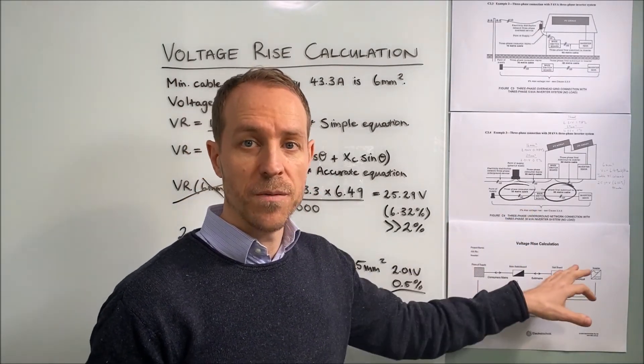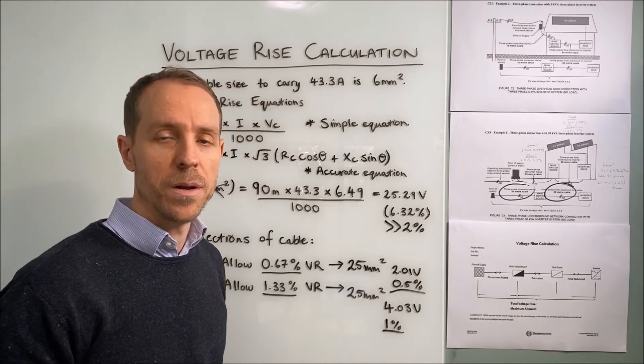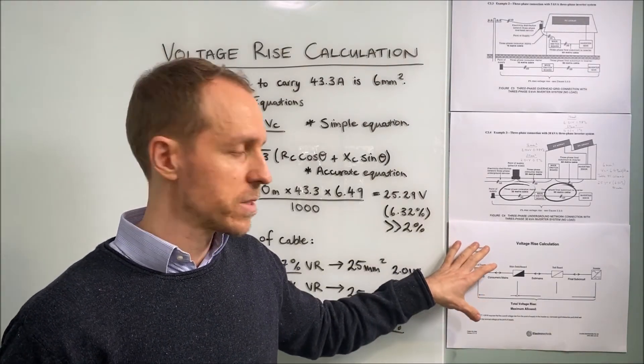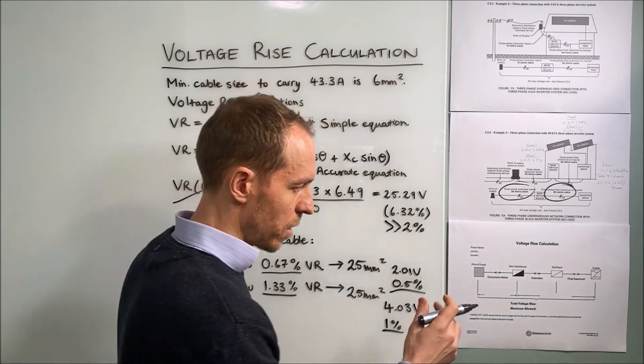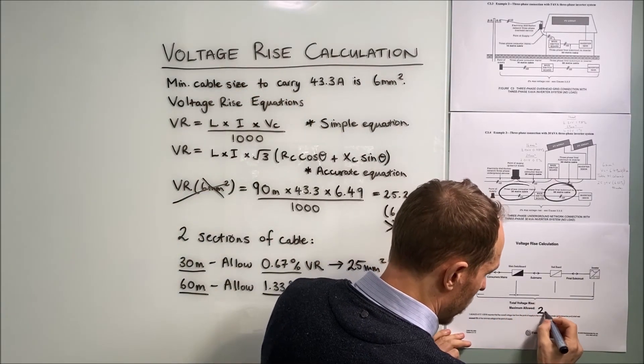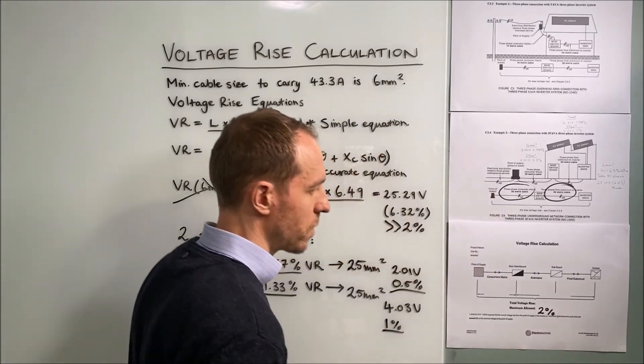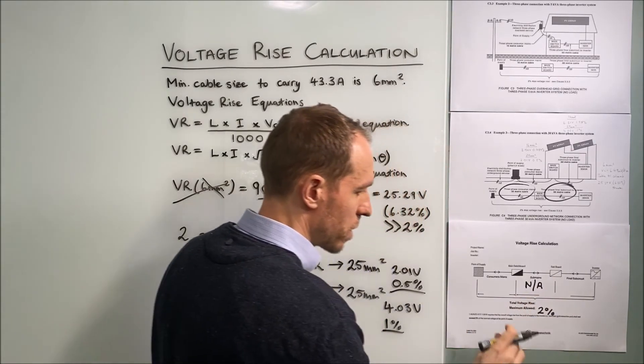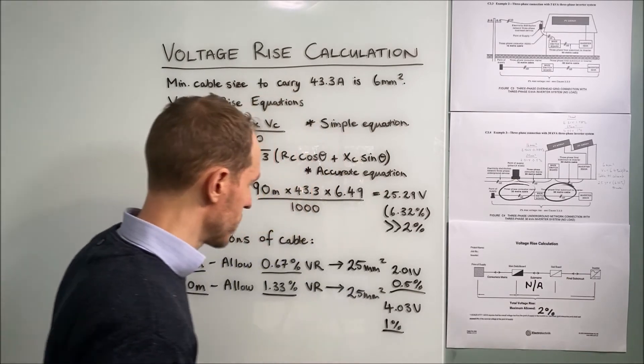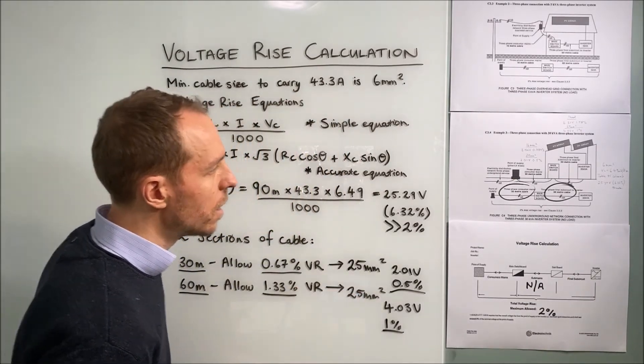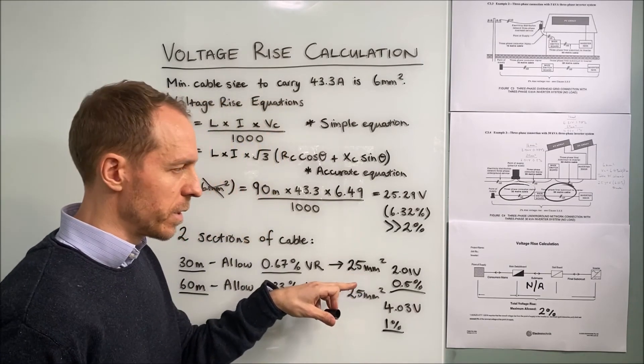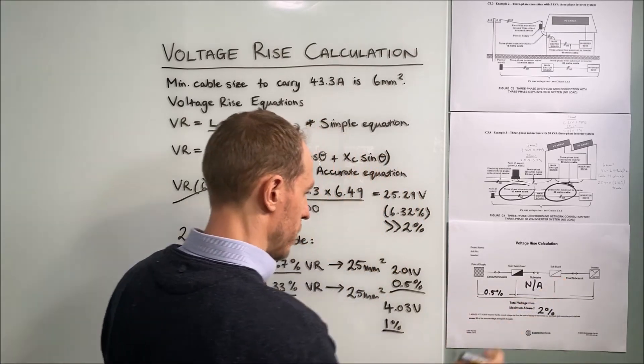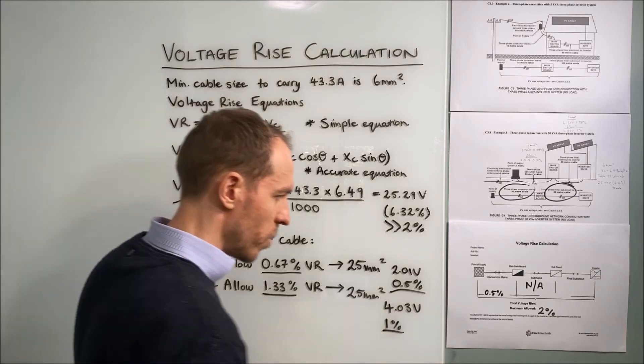Now, if you are producing a voltage rise calculation report for your power authority, it might look something like this. This is the output of our software. So you would have a maximum allowed limit of 2%. Now, sub mains section is not applicable in this case. We have a consumer's mains and a final sub circuit. Our calculated voltage rise for the consumer's mains was 0.5%. And over here for our final sub circuit, we have 1%.